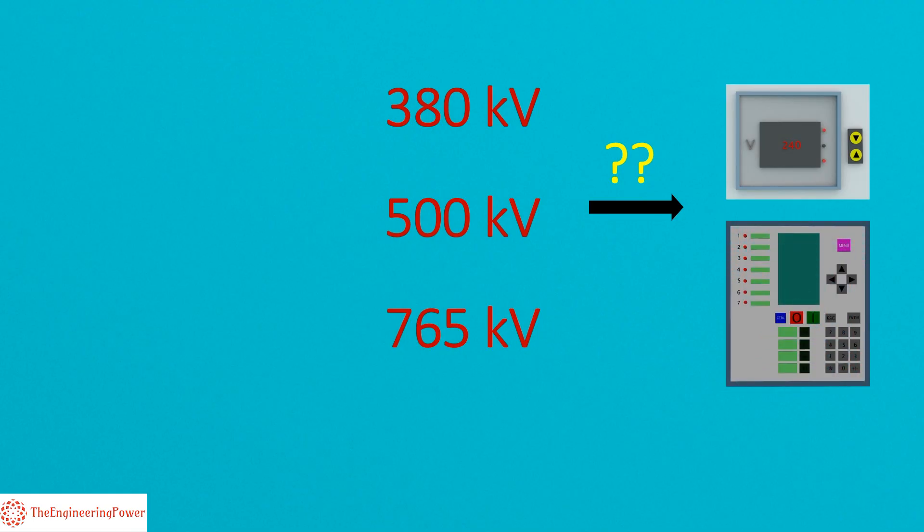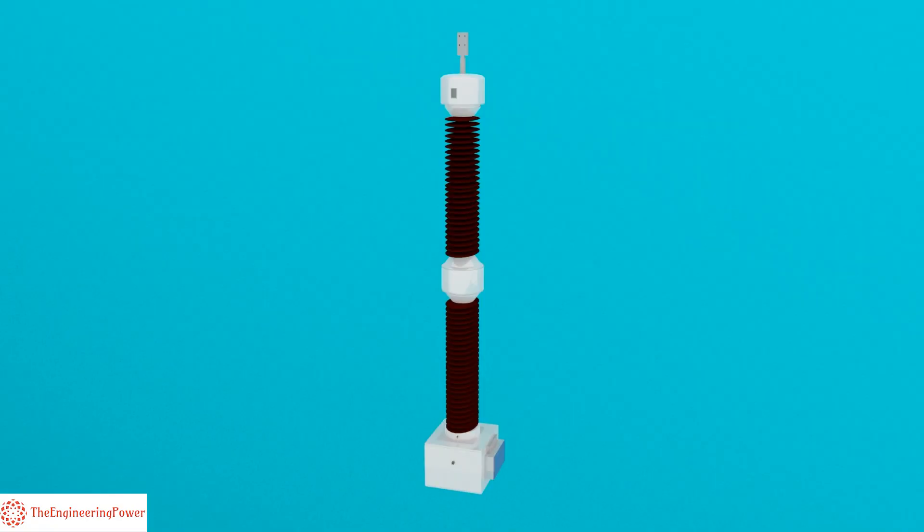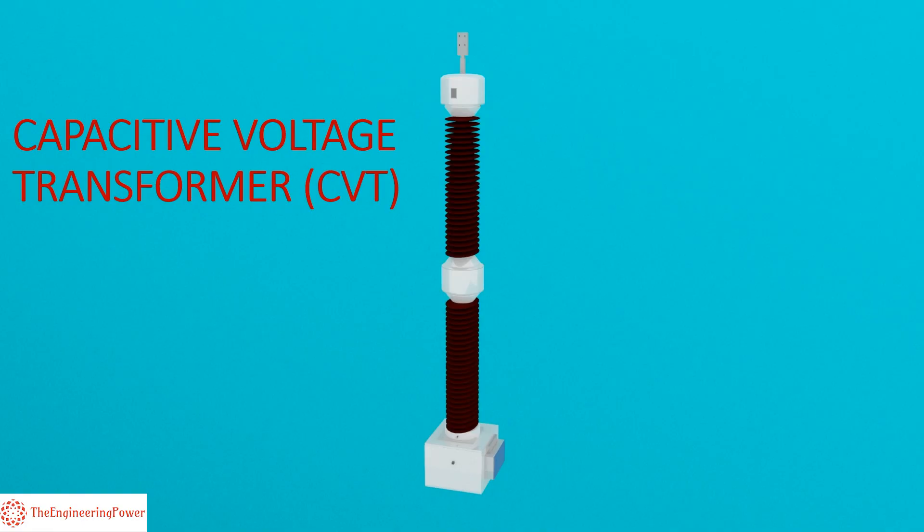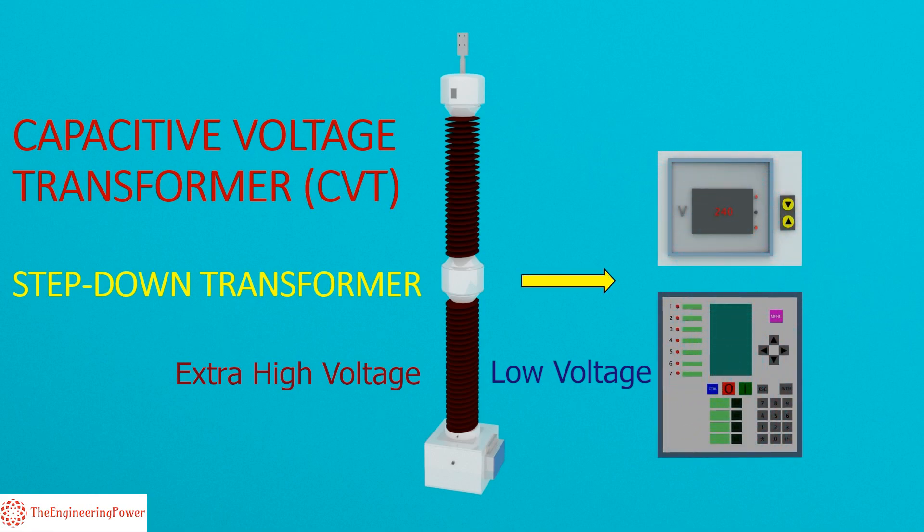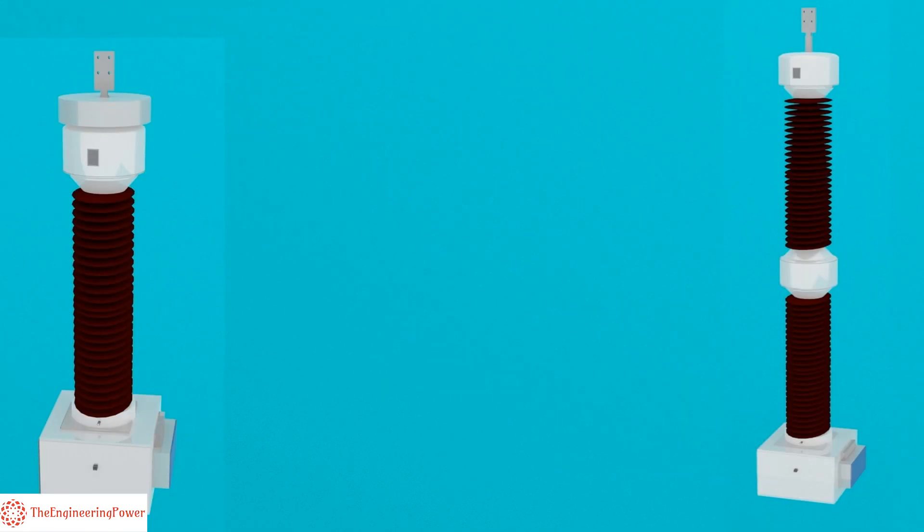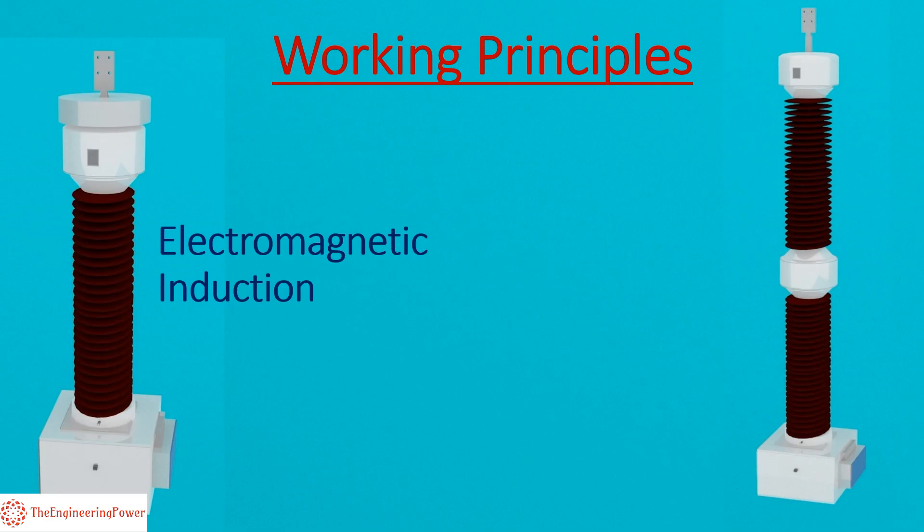The answer is Capacitive Voltage Transformer or simply CVT. Similar to a potential transformer, capacitive voltage transformer is also a step-down transformer. It transforms the extra high voltages to a safer lower voltage that can then be fed to relays and meters. The basic difference between a PT and CVT is their working principle. PT works on the principle of electromagnetic induction, whereas the working of CVT is based on the principle of voltage division and electromagnetic induction.